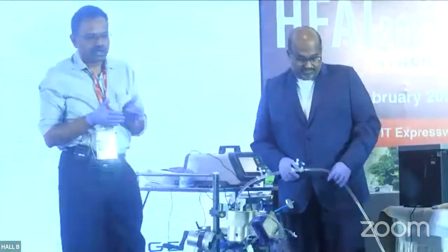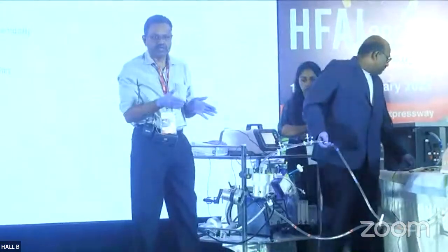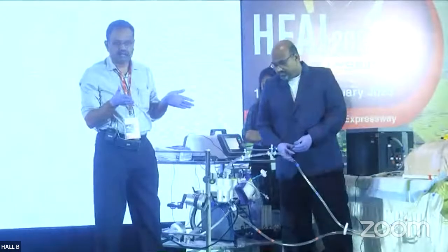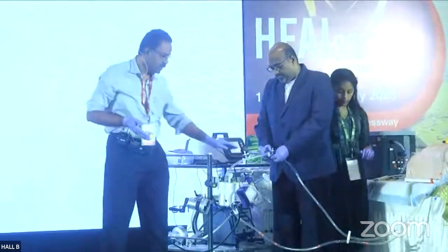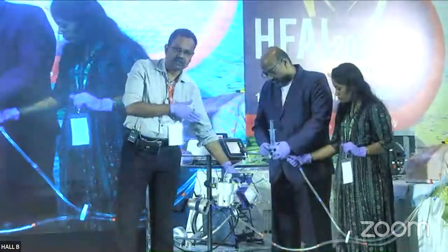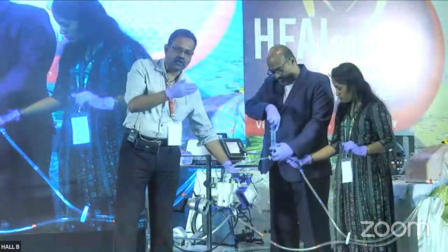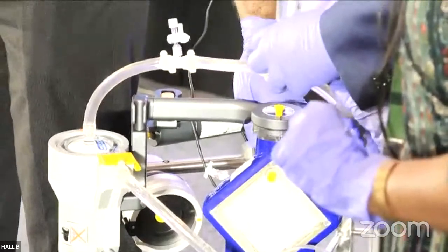The trend in P2 and P3 is very important. You monitor the pressure in P2 and P3. Normally the difference will be less than 30. If it goes up, it means there is some resistance offered by the oxygenator and some blood clot formation in the oxygenator. If the trend gradually climbs, for example, today you see 30 and the next day 40, then you have to suspect clot formation in the oxygenator.